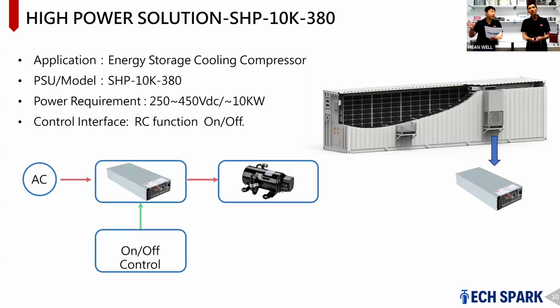That's to keep the battery within the high efficiency range it operates in. Because it's a lithium-ion battery, especially when it's too cold or too hot, it won't be able to fully charge or fully discharge. So it's better to keep them between 25 to 40 degrees Celsius. That's why the customer has to design their own cooling system. For one container, they might choose the XP30K to power two cooling systems to regulate the temperature.